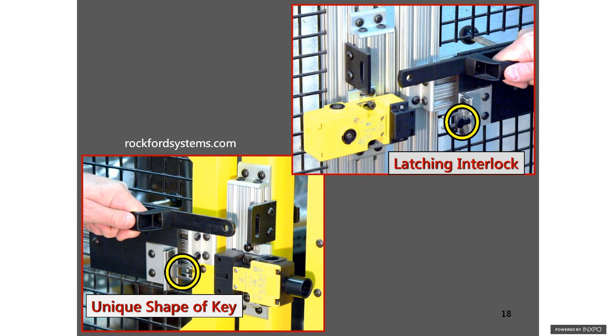Now, the guard interlocks today are not only requiring a unique geometry on the key, which is shown at the lower left, but some also have a latching feature, like the one at the top right. So when you latch the door shut, there's an electric solenoid inside that yellow switch that grabs the black tab and holds onto it, won't let it go, until the hazardous motion behind the guard has come to a stop. Latching or locking interlock switches are some of the newer technology that the 4 or 5 major manufacturers of interlocks all offer.